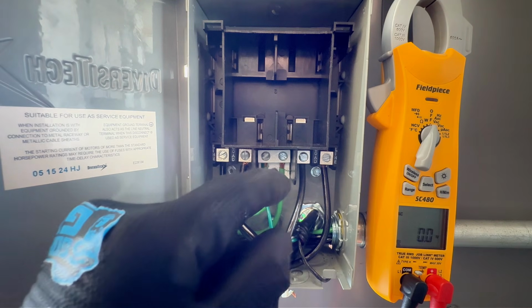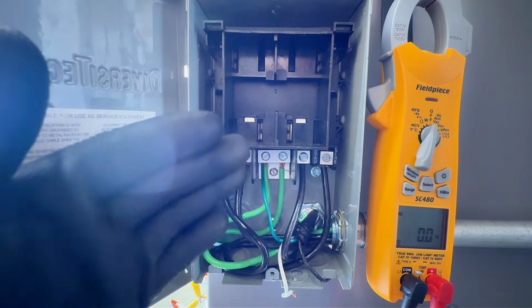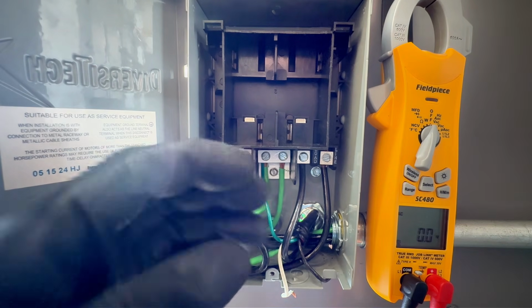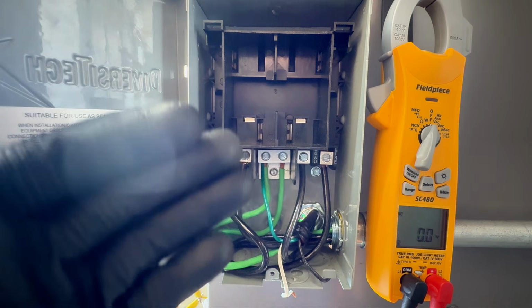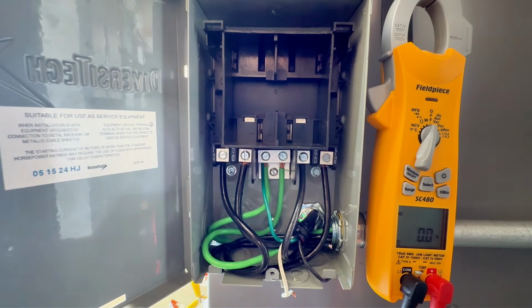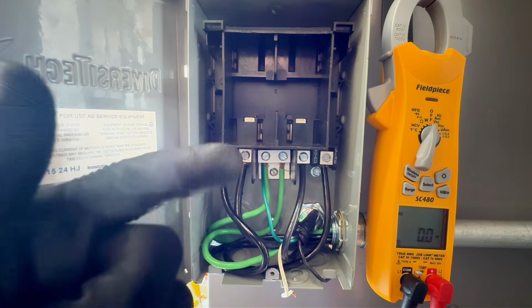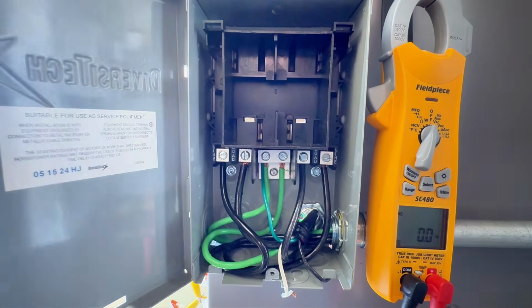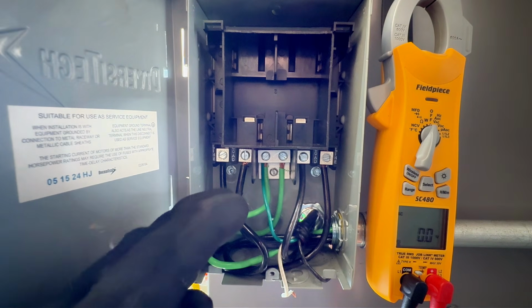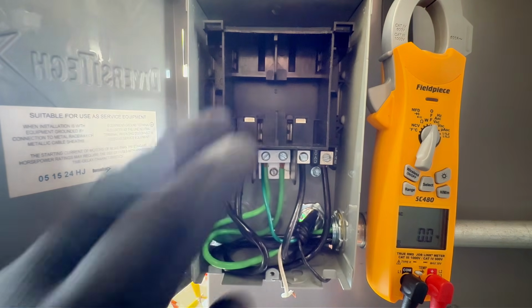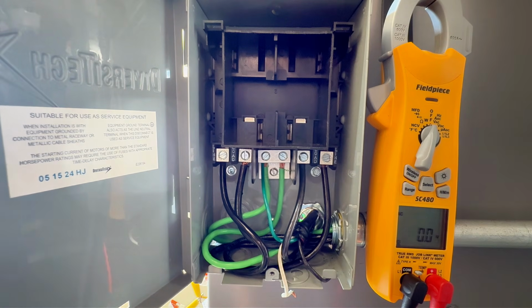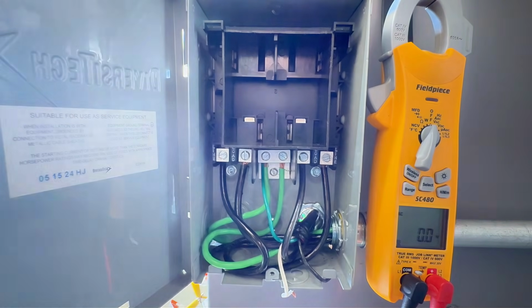So what can cause a disconnect to burn up, or show burnt marks? Let's say you are dealing with a disconnect that supplies a furnace. It can be a 120 volt disconnect, or a high voltage disconnect where you have something like 208 volts, like this disconnect right here. And let's say all your loads are okay: your compressor, your condenser fan motor, your indoor motor, anything that's going to pull a lot of current. Nothing is shorted to ground, and none of these lines are touching the metal. Everything checks out, but something's going on with your disconnect. You find that maybe your fuses are going bad, like I said, fuses go bad, and there are a lot of burnt markings.